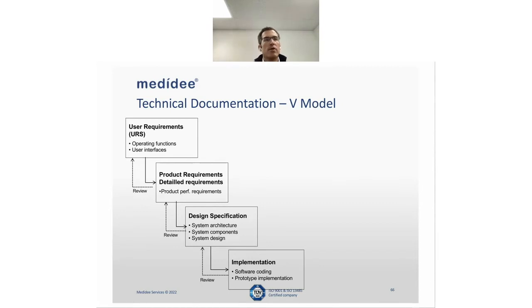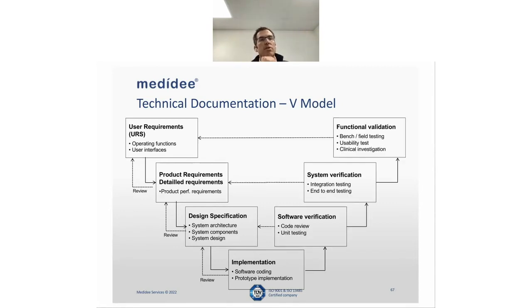And once you have done that, you're going to come up the other side of the V, which is basically performing all the verification and validation. So you're going to implement different levels of testing and verification. Typically you're going to do code review, unit testing, and maybe exploratory testing in some cases, to check that the spec is actually achieved. Then you're going to do verification to be sure that the functions you planned to have are there. And at the end, the functional validation will demonstrate that the intended use, what your device has been conceived for, is able to be achieved.